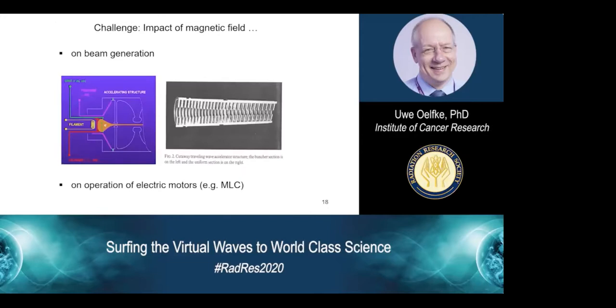There are two major challenges coming from the impact of the magnetic field on the operation of the LINAC. First, the beam generation. You see here the electron gun of a LINAC. Here's the filament emitting the electrons. And of course, there's an extra Lorentz force on a moving electron beam. This electron gun would not be able to emit the beam into the waveguide, which is then used later to produce the Bremsstrahlung photons. Furthermore, the magnetic field will have an impact on the operation of electromagnetic motors, for instance, of the MLC.